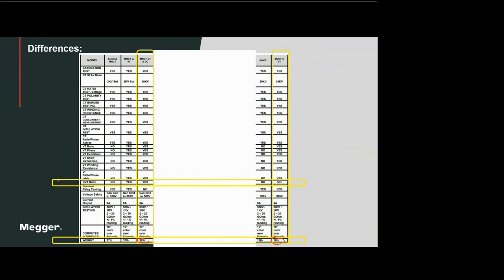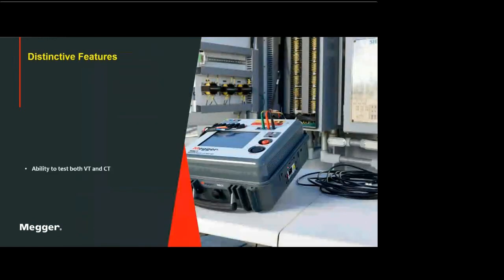And the other difference is that the MRCT can do CVT ratio, or we can test capacitive voltage transformers, unlike with the MVCT, where we cannot do the CVT. Well, anyway, the CVT is being used only on the transmission line or the higher voltage system. So if you are a utility company or a distribution utility company, then you don't need the MRCT, but the MVCT will be enough.